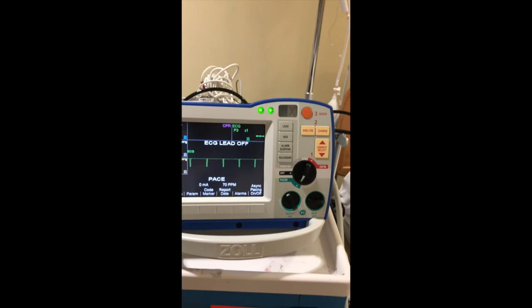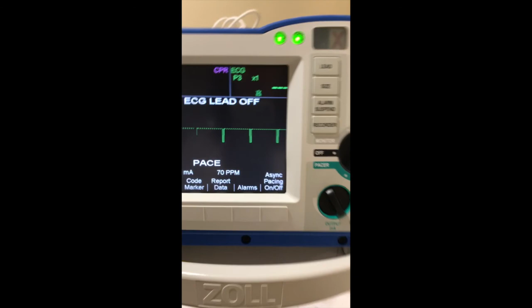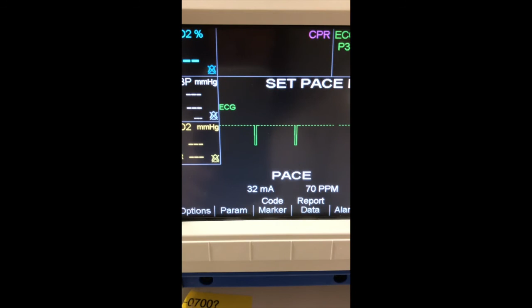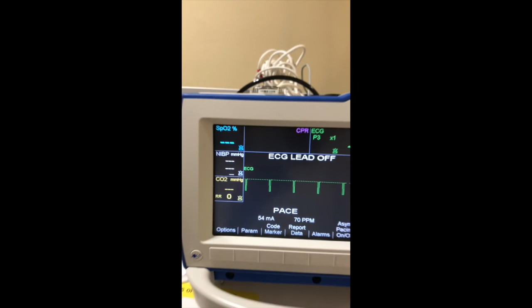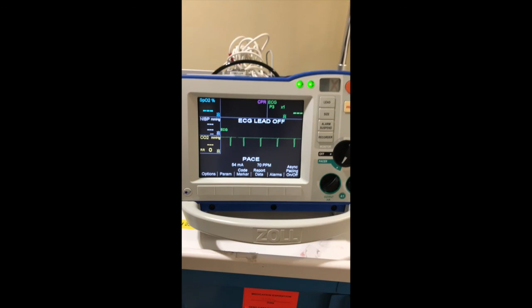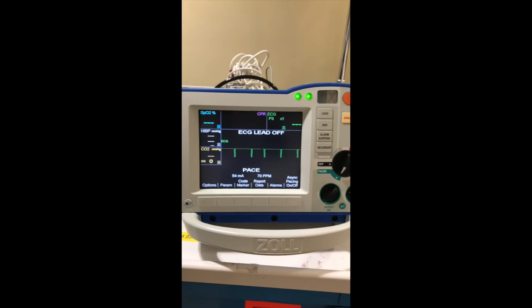So the next thing you're going to do is you want to be able to achieve capture. And the way in which you do this is through the milliamps, as you can see here. So what you're going to do is increase your output or your milliamps until you achieve capture. You'll see them increasing here. It's usually patient dependent. And essentially what capture is when you have a pacing spike and then you have a QRS with every pacing spike. That is when you achieve capture. A pacing spike and then a QRS with each spike.